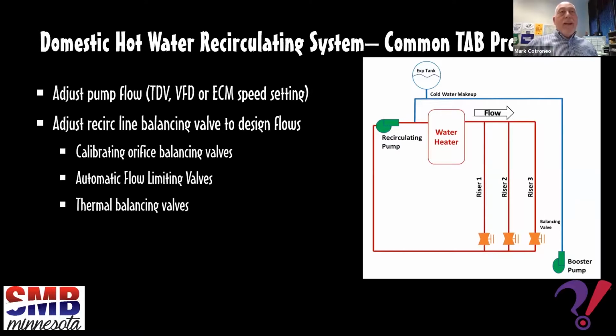The process to balance the domestic water system is similar to the hydronic system: measuring the shut-off head of the pump and then the dynamic head of the pump and plotting it on a curve. Then we would go through each recirculating balancing valve and set it to the required flow for that branch. Auto flow valves are verified by measuring the required differential pressure. Sometimes thermal balancing valves are used on the system. This does not allow for any measurement or adjustment. If that is the case, the pump speed is set, with the hope that the owner is happy with the operation of the system.